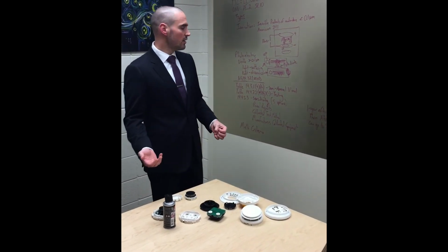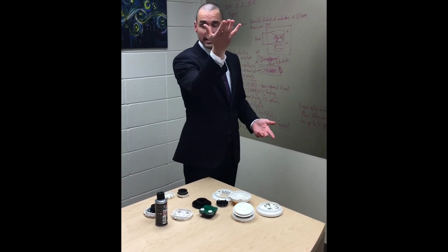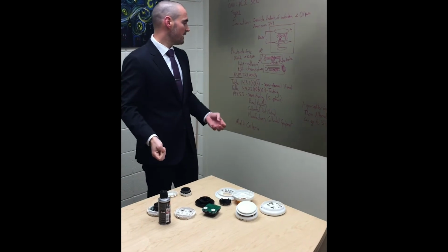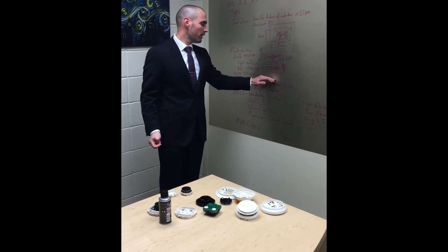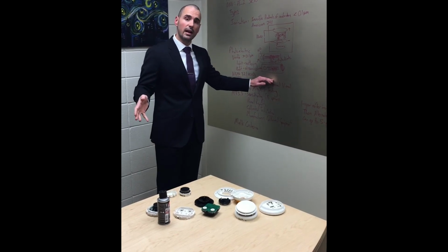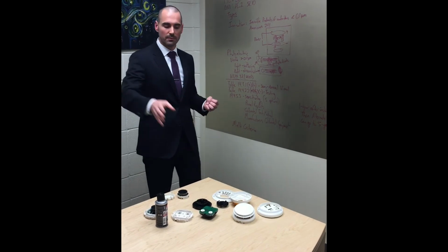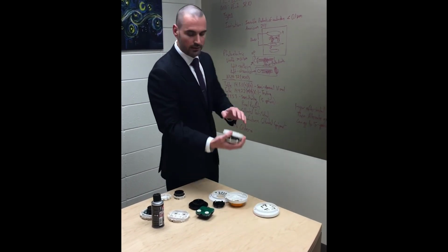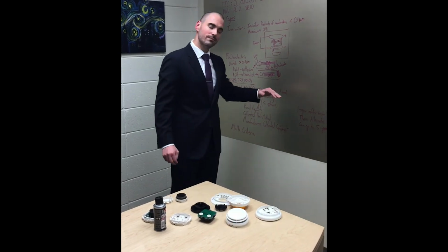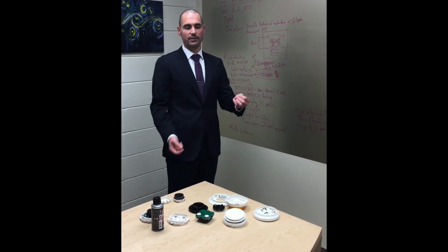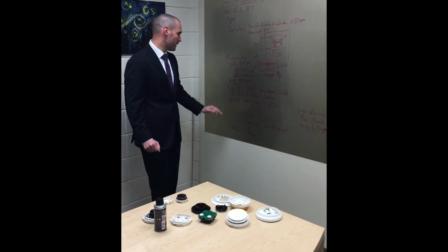What we're looking for is that the smoke detector is intact on the ceiling and doing what it's supposed to. The most common issue in hospitals is that during construction or painting, people will cover these up with gloves, tape, all kinds of stuff, and often forget to remove those things. So that's really the main purpose of the semi-annual inspection.